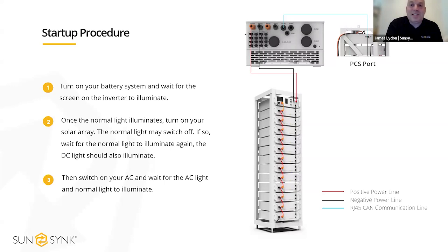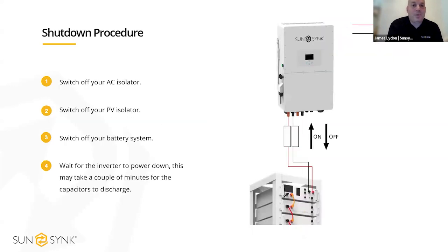So yeah, with everything else isolated, that will allow you to make sure your batteries are connected correctly. And on the inverter, in the settings, we have a screen that says Li-BMS, and you can press on that and it will show you all the values of the connected batteries. So the temperatures, the voltages, max charge and discharge current. In that way, we've got really good comms with the batteries, and you can then introduce the DC and then introduce the AC. So you're good to go.